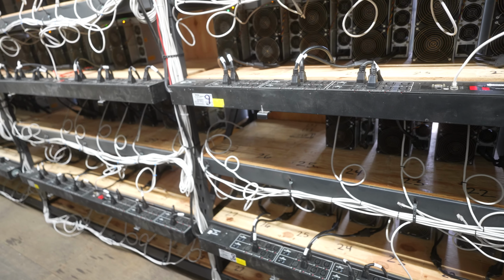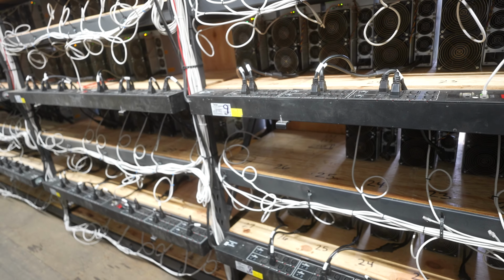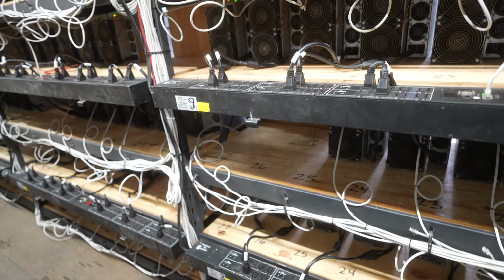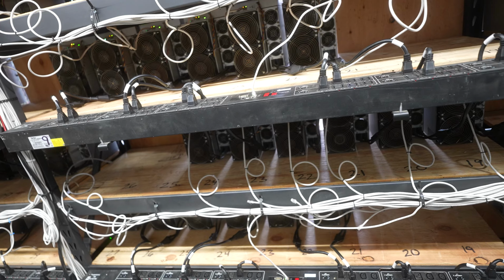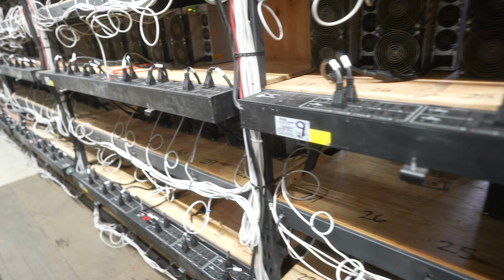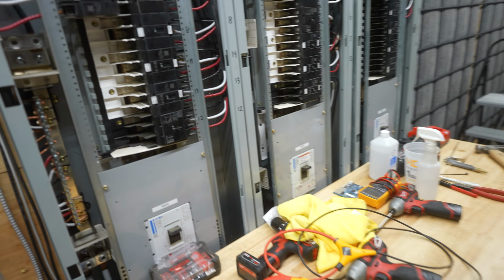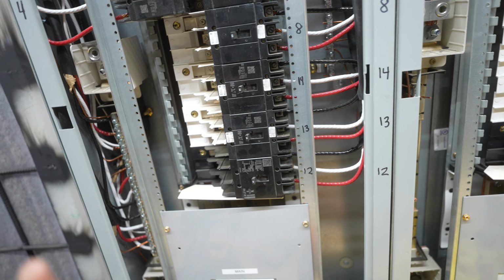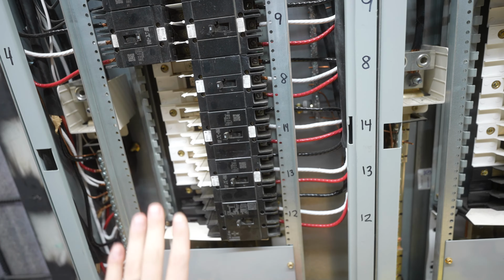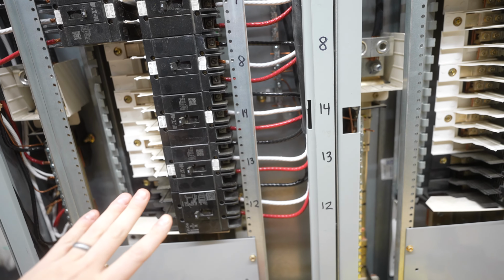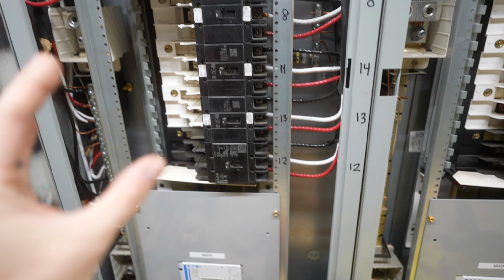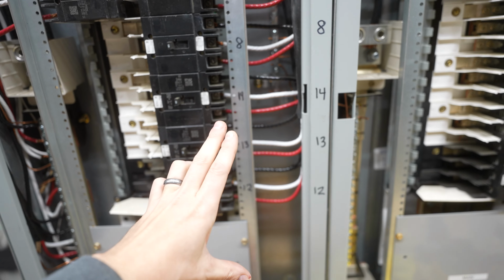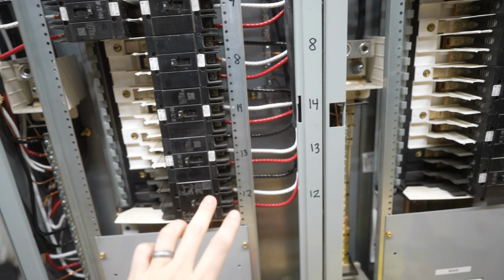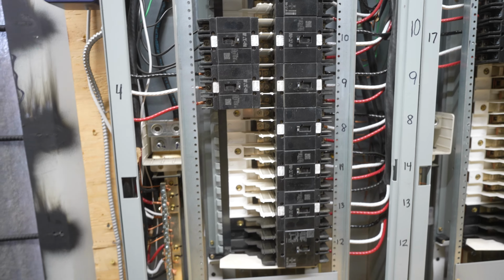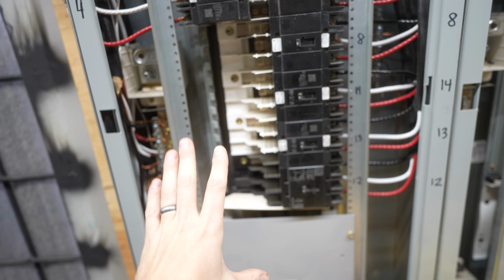We do that because it's more economical - the hotter your copper, the more watts you're wasting. So we make sure our copper stays nice and cool, meaning we never overload it. It's also for the infrastructure - we don't want any problems in the future. We've got to keep this running for the next 20 years, and the way you do that is by building it properly: proper breakers, proper copper, proper load, never overloading it, so your panel can stay like this forever.